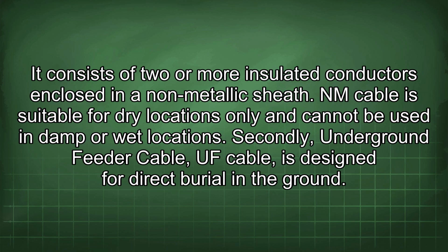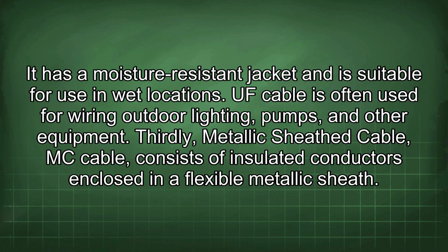Secondly, underground feeder cable, UF cable, is designed for direct burial in the ground. It has a moisture-resistant jacket and is suitable for use in wet locations. UF cable is often used for wiring outdoor lighting, pumps, and other equipment. Thirdly, metallic sheath cable, MC cable, consists of insulated conductors enclosed in a flexible metallic sheath.